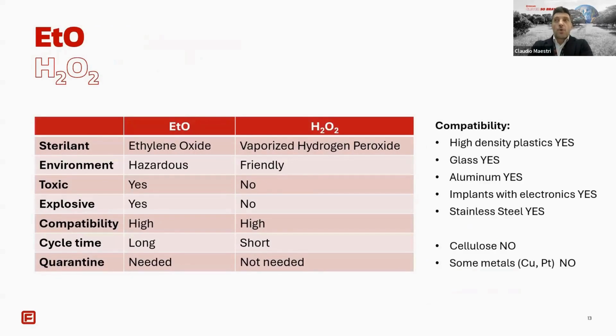Let's compare EtO and H2O2. For sure, from the environmental point of view, H2O2 is much more friendly than EtO. H2O2 is not toxic, is not explosive. Both have high compatibility, as we already saw. The cycle time using H2O2 is much shorter than using ethylene oxide. And another important advantage of using H2O2 is that quarantine is not needed with H2O2.